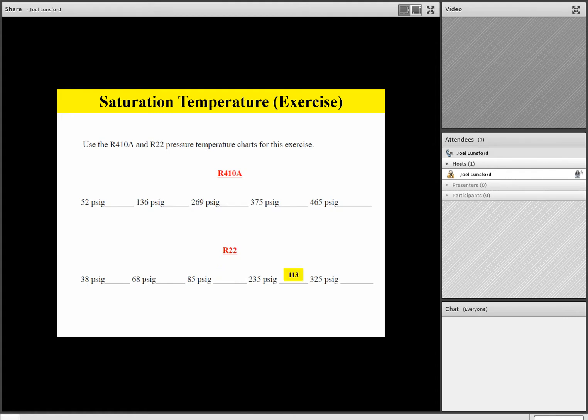And our final example off our pressure temperature chart at 325 PSIG for R22, what's the pressure temperature conversion, please? Good, about 137 degrees. So team, this is important. We need to be able to refer to the pressure temperature chart because some of the things we'll be looking at here shortly in our module will be superheat and subcooling of the evaporator and the condenser coil. And so we have to be able to find pressure and temperature readily and quickly, the pressure temperature conversion, because that's an important key point in finding superheat and subcooling on our evaporator and our condenser coils.